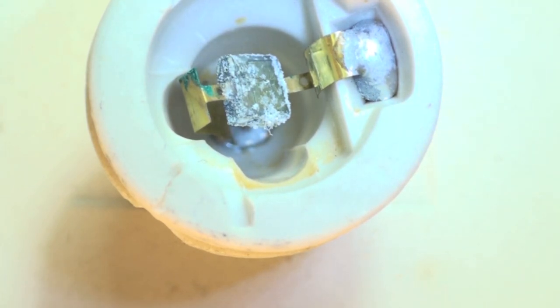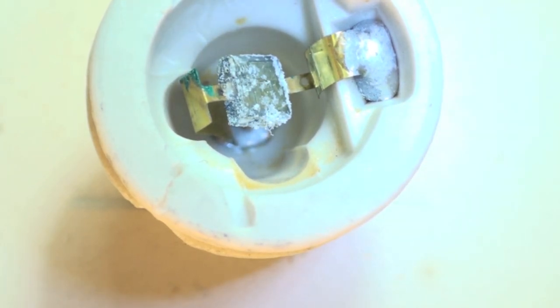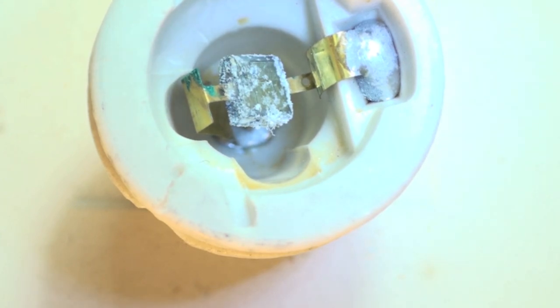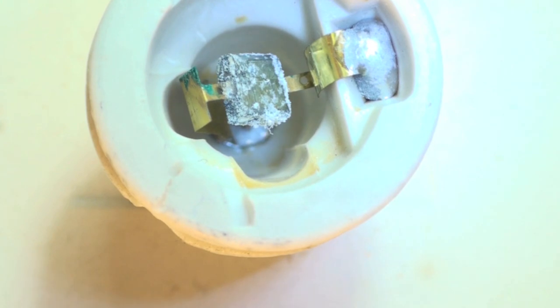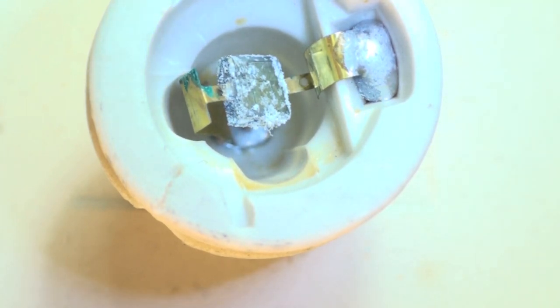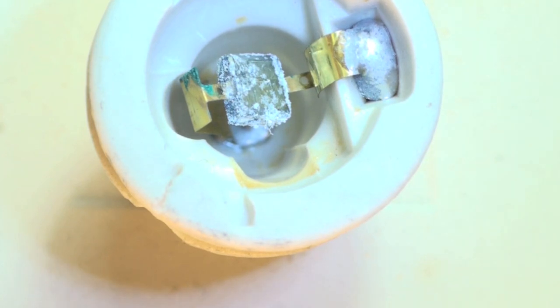If I had a motor draw, this thing's 15 amps. If I had a motor draw of say 25 or 30 amps on startup, this would not blow. If it was a standard fuse, it would just blow. But because those little thin pieces are big enough to handle more than 25 or 30 amps, maybe up to 40 amps, they won't burn in two.